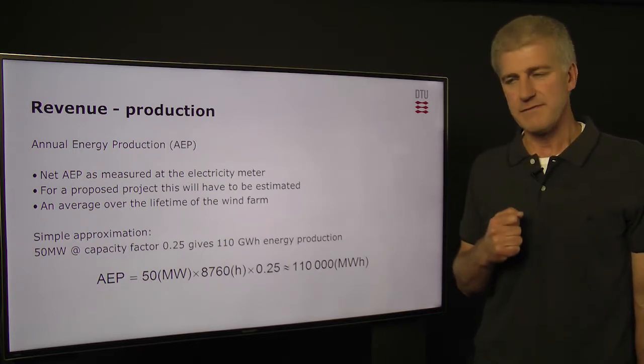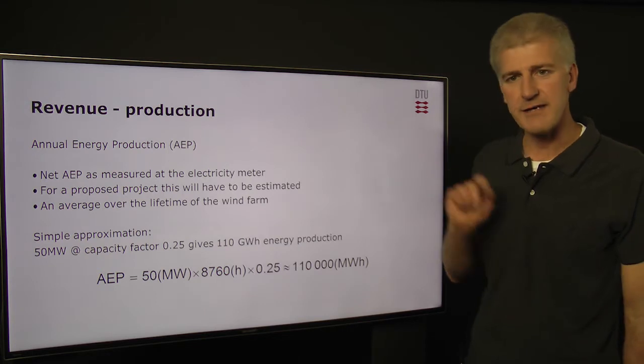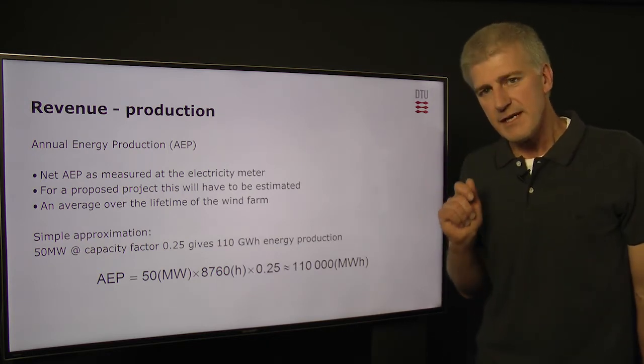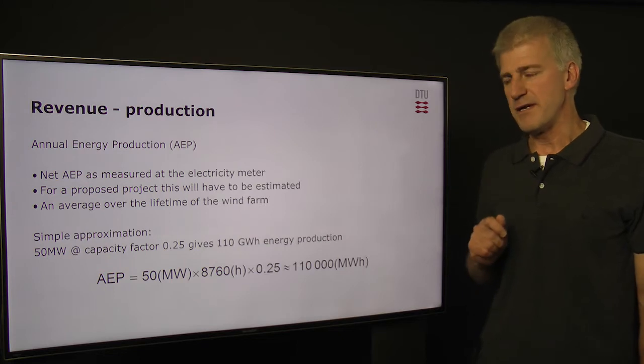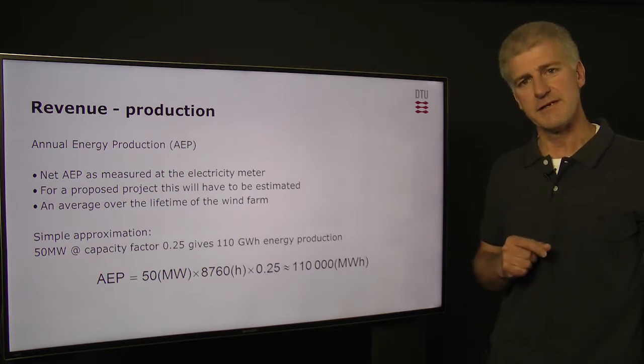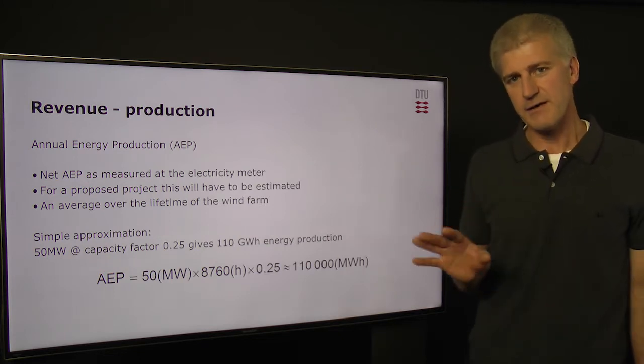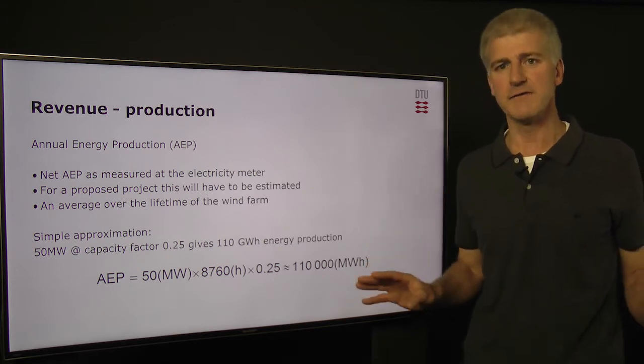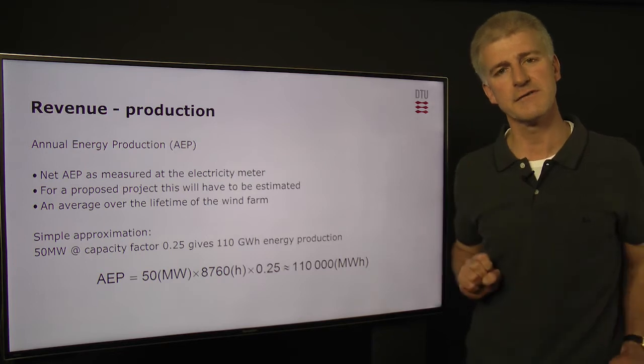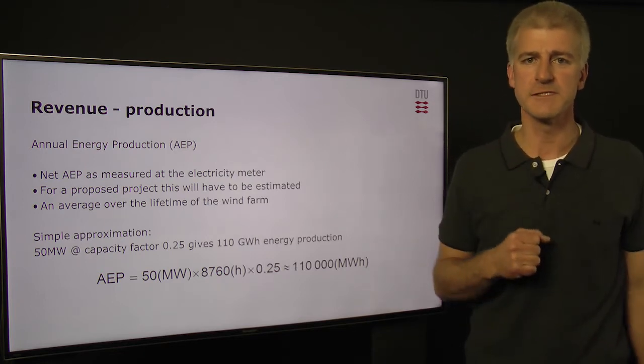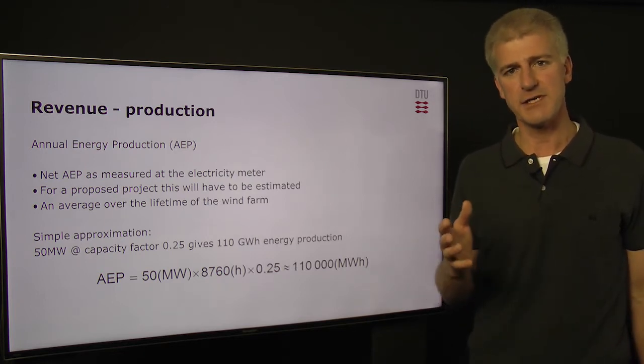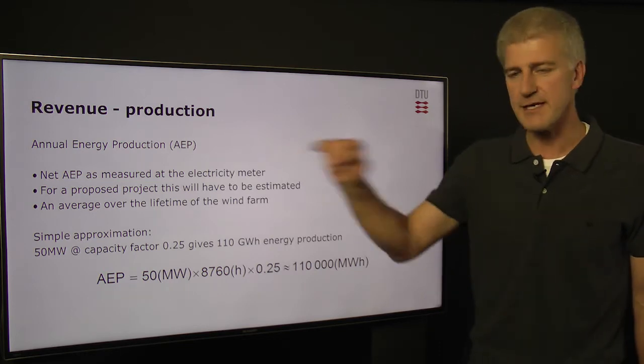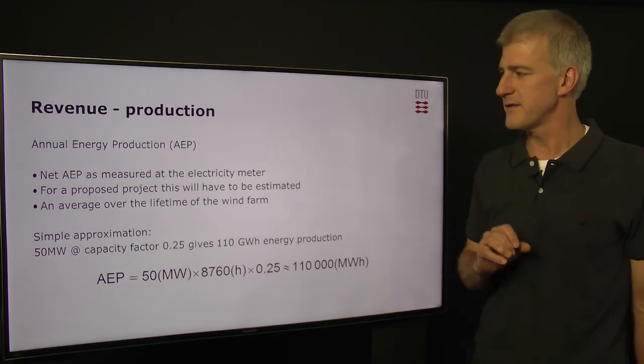On the production side of things, the key figure here is the annual energy production. We need the net AEP as measured at the electricity meter. This means we can't use information from the wind turbines themselves, because we have losses through the cables, transformers, and switchgear before we actually get to the public grid. So we need to take it as a net figure at the meter.